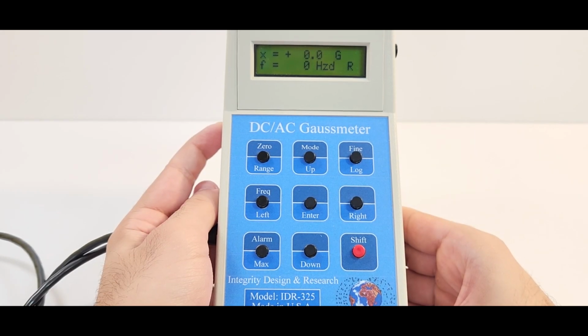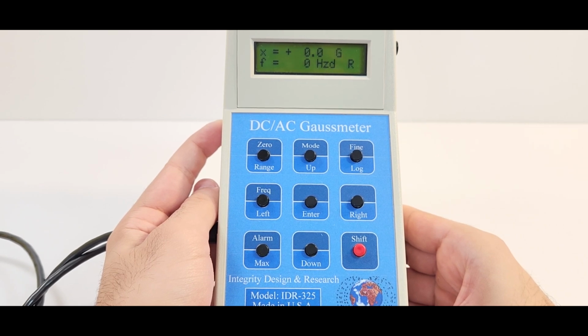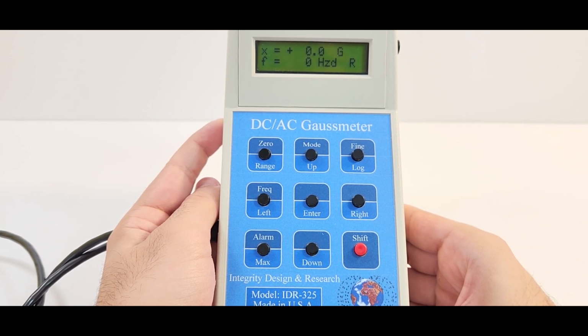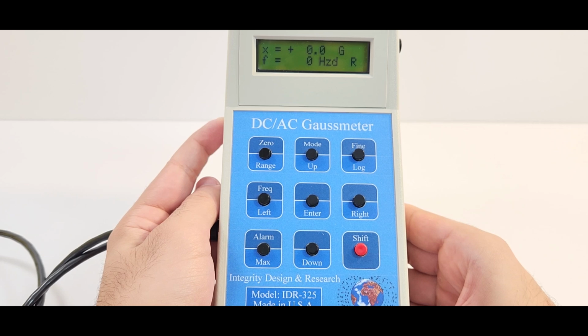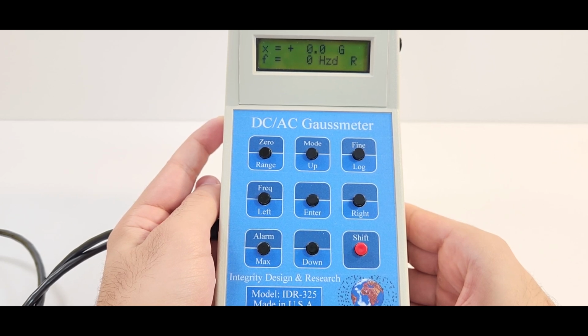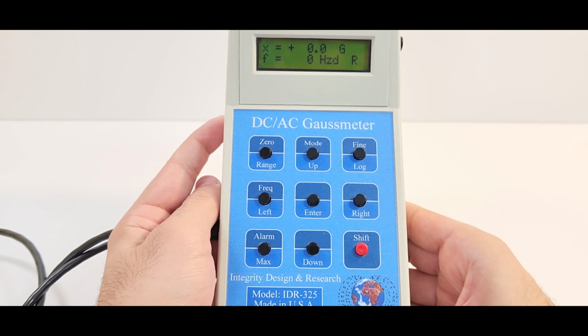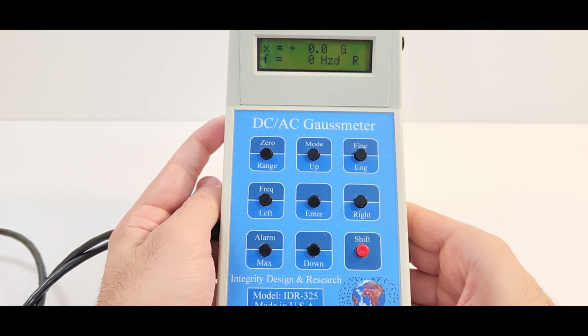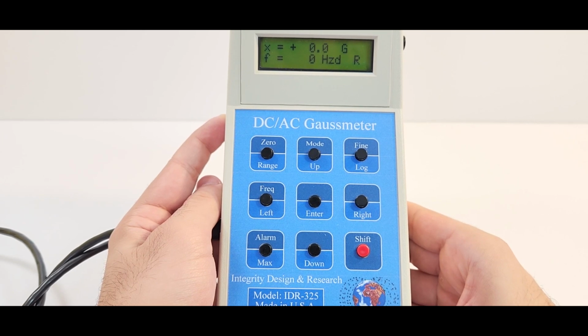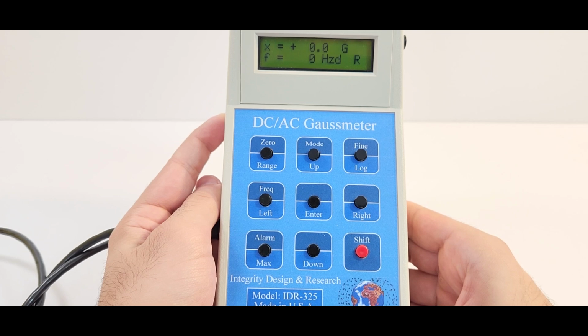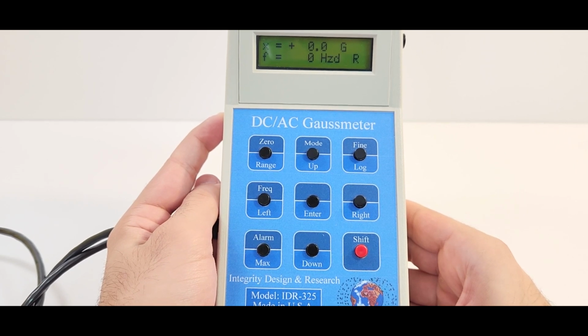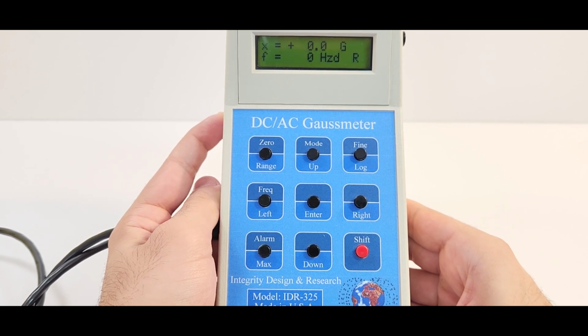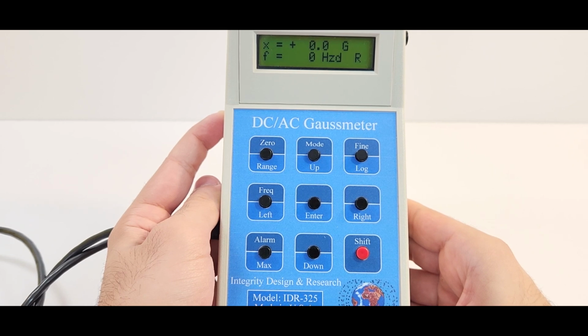The IDR 325 comes with additional features. An alarm can be configured to go off at a specified magnitude. This is particularly useful for medical and industrial applications. The AC frequency can be displayed alone with the frequency button, and the unit can be set to a max function, which will read and hold only the highest values read. In this scenario, select the nearest scale prior to measuring, and don't select auto scale. The meter can also log values and view them. For instructions on this type of function, please refer to the manual.